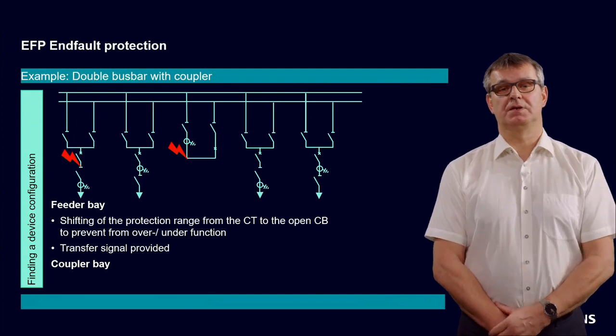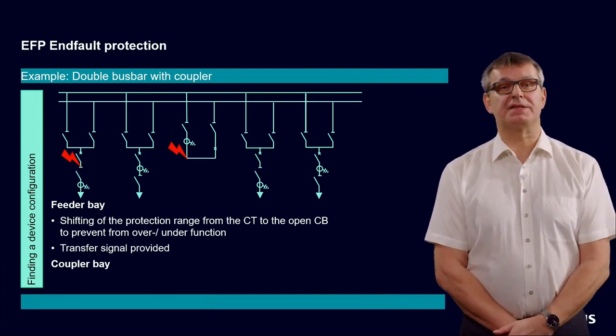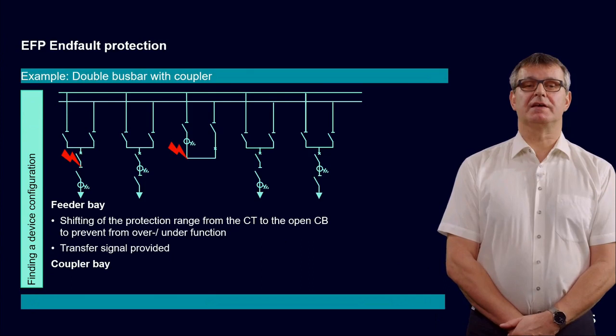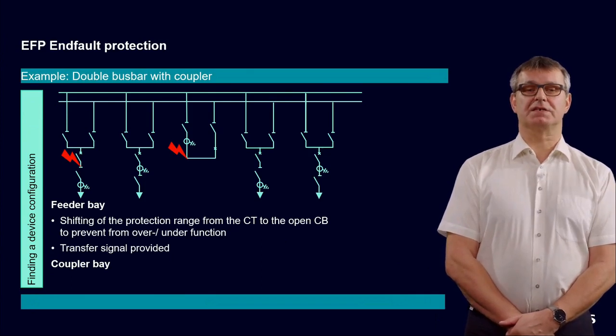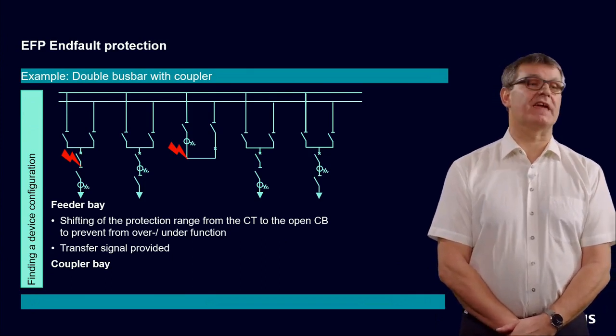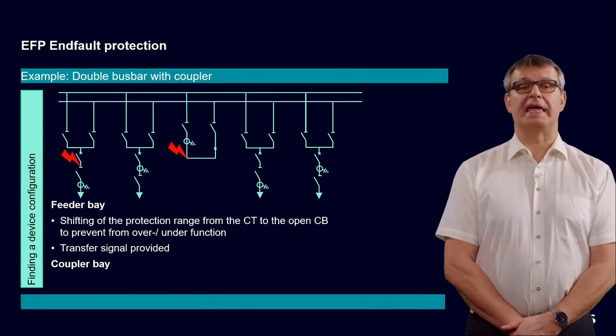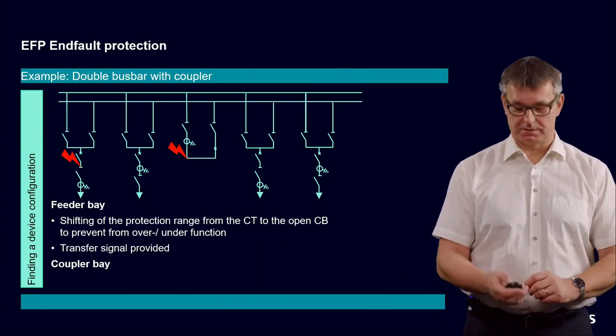In a coupler bay, the end-fault protection will also protect, in case of an open circuit breaker, the area between the current transformer and the open circuit breaker.